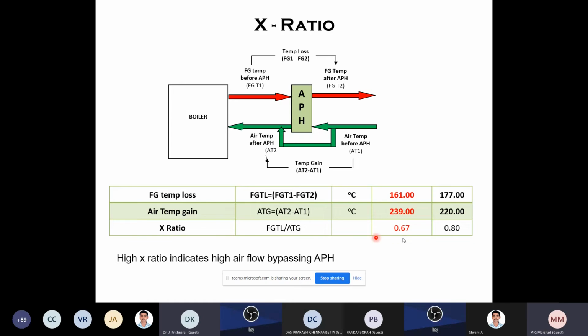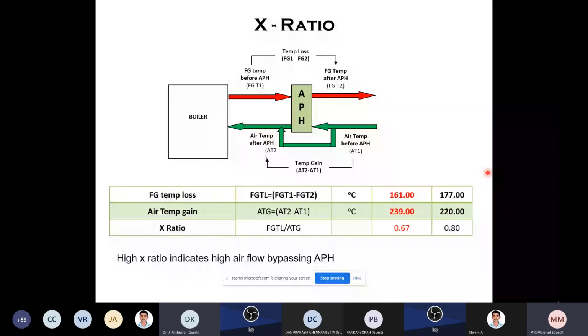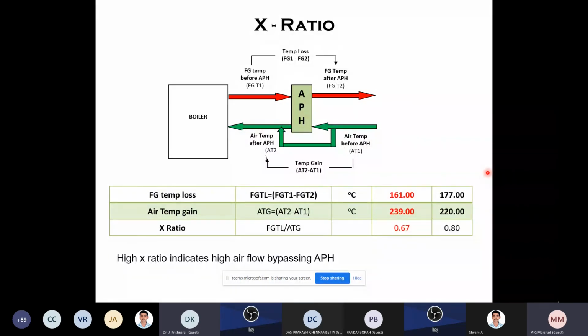There is some standard value, but it is not a standard all the time. It should be as low as possible. You see the standard is 0.67, but here it is 0.8, higher. That means there is an air leak, there is bypassing. So this is called the X ratio. These are the three parameters you have to check in the air preheater so that you are able to identify the condition of the air preheater. Is it okay?